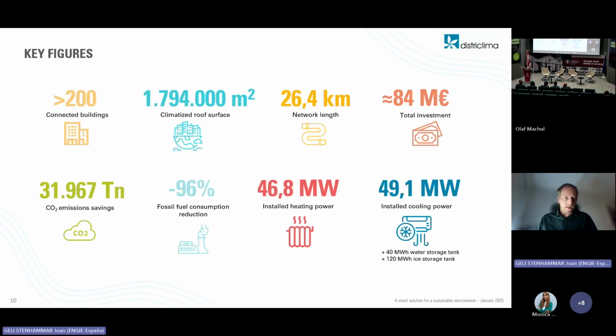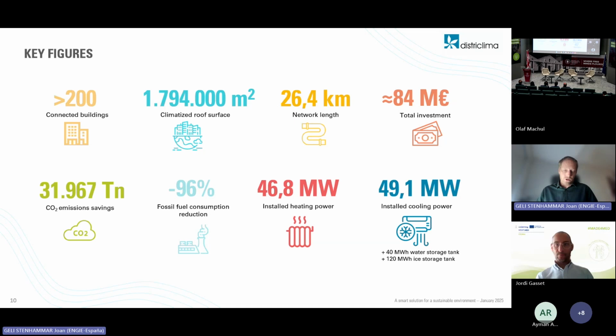So coming to the key figures of the Districlima network, you have to understand that it's a dual network, both for heating and cooling, and we now have around 200 big buildings connected, with a length of 26 kilometers and a total installed capacity of around 50 megawatts in heating and 50 in cooling. In cooling, in addition, and that's the focus of this collaboration with Storm Project, we have accumulation both in cold water and an ice storage tank.